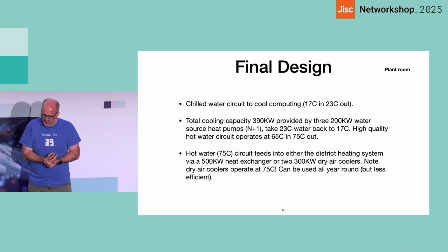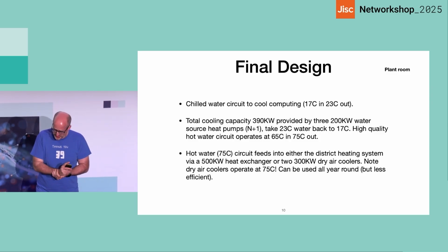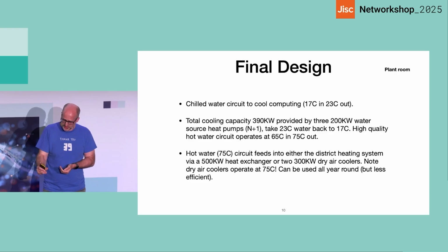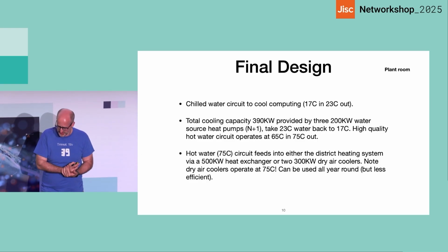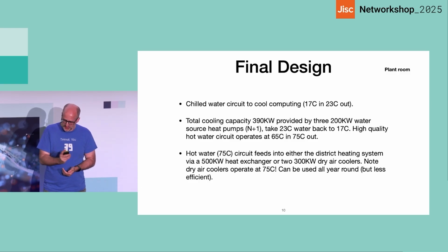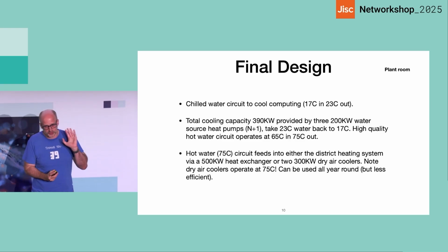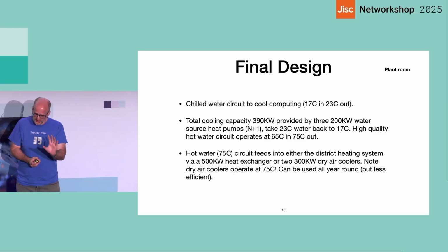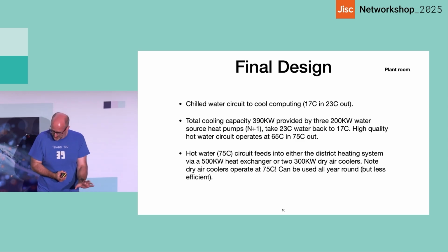Interesting stuff upstairs. So in the plant room, because we have a chilled water circuit going through the in-row coolers that do the cooling in the air or in the data center, that not so chilled water goes back up into the plant room at 23 degrees. Then we have a cooling capacity of 390 kilowatts. To do that, we have 3 200 kilowatt water source heat pumps. So we have an N+1 redundancy there, and that takes that 23 back to 17, which will then go back downstairs. And then that also produces what we call a high quality hot water circuit of basically 75 degrees, which can go directly into a district heating system via a heat exchanger, which is very close by.